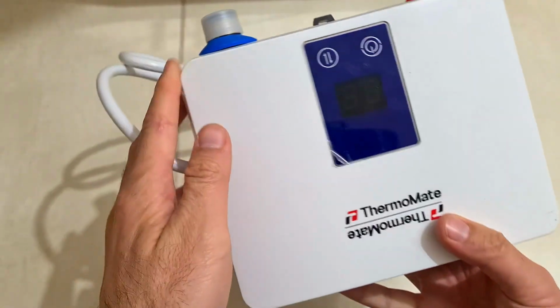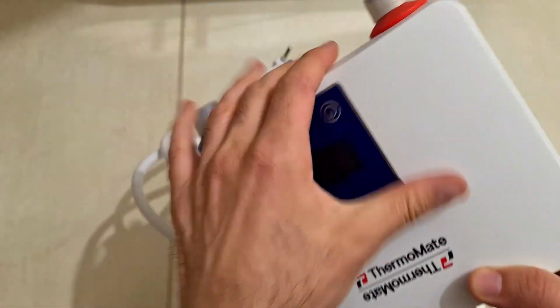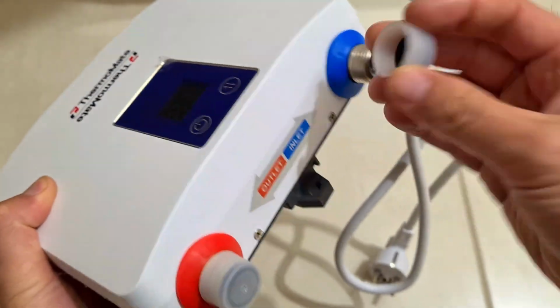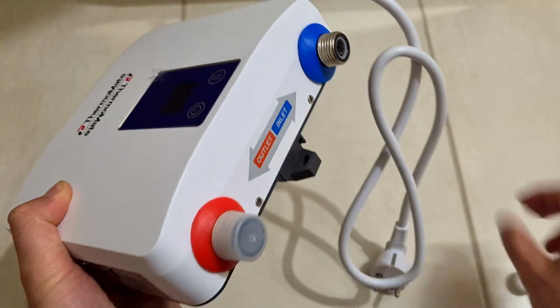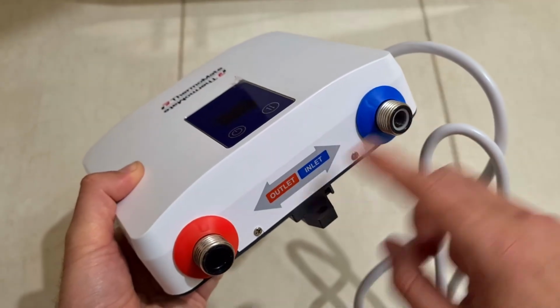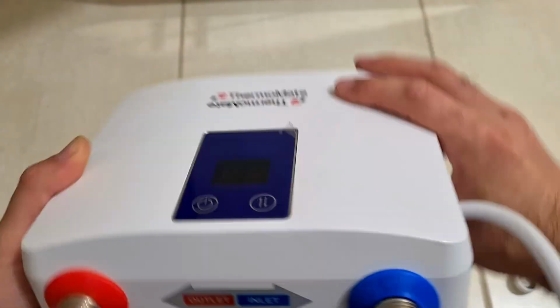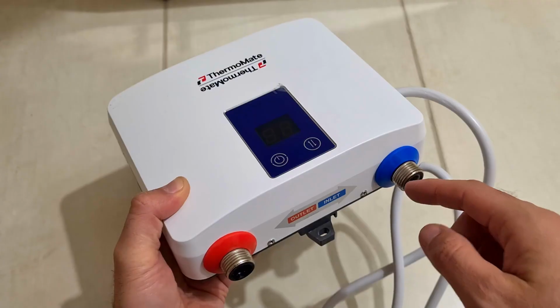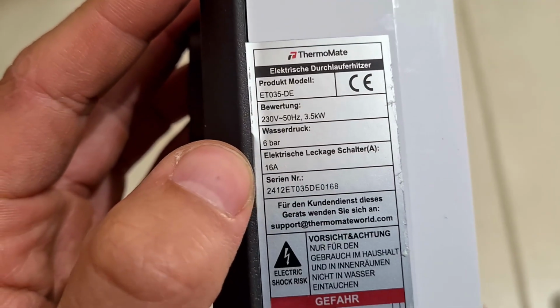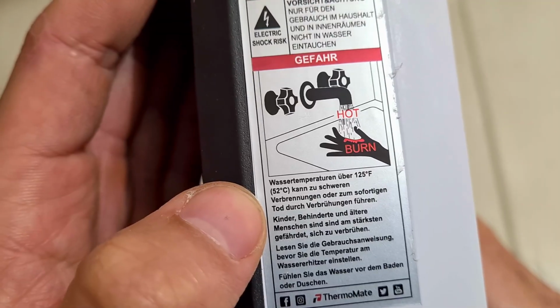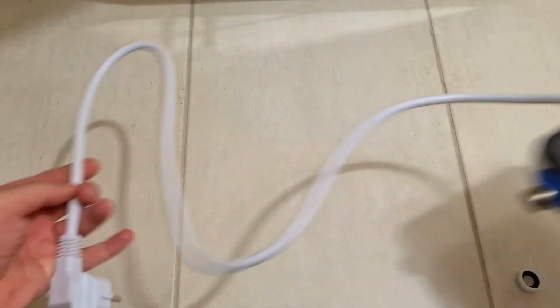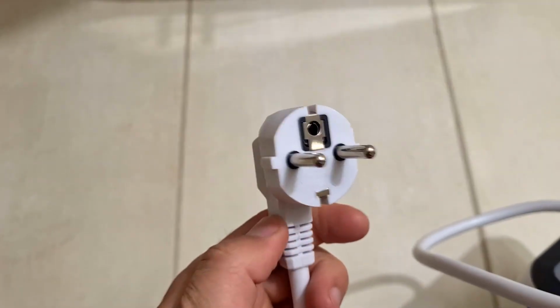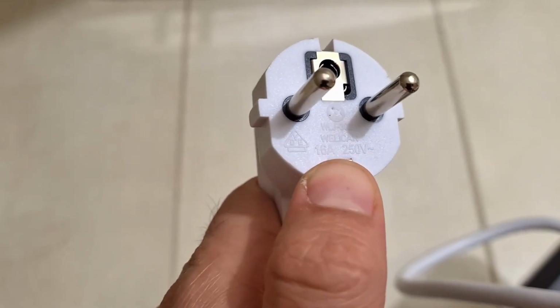ThermoMate upside down, so I guess you can mount it in any direction. You can remove these. They have a rubber inside. If I blow air in on one, the air exits on the other one. Nothing is blocking the airflow. On the left side we have some other details. Model 6 bar, 16 amps, 52 degrees Celsius is mentioned here. The cable itself is quite short, around a meter, 220 volts, 16 amp is mentioned here also.